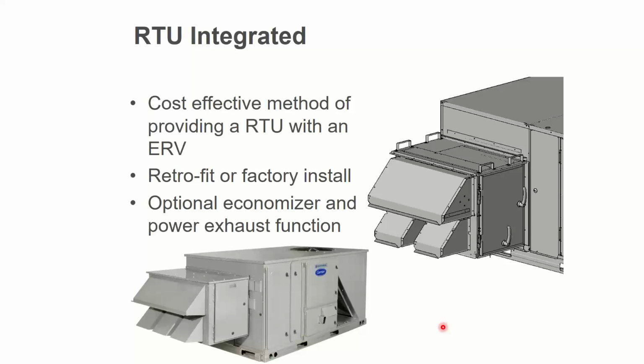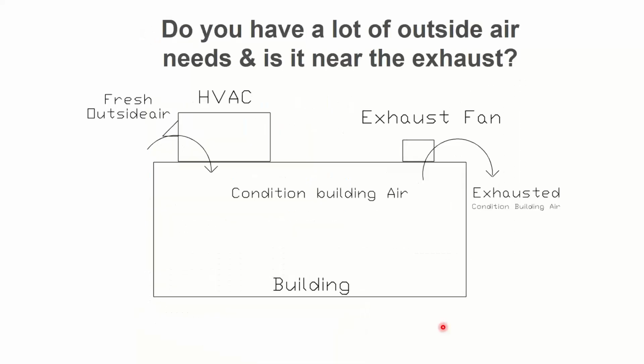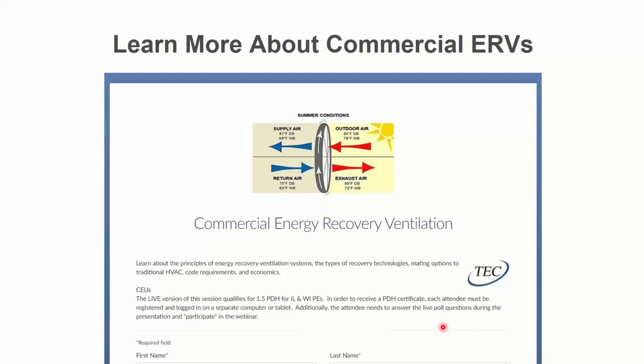And then there are small ERVs that you can bolt onto the side of an existing rooftop. We don't do that very often for the simple fact that most rooftops are already oversized. And when I put an ERV on, I need less cooling, so that makes that problem worse. Sometimes we do it when there's a change of usage of the space. Hey, this used to be an office building. Now it's going to be a fitness center. We need more tonnage and we need more fresh air. What can we do? Well, you can possibly keep the existing rooftop and add an ERV onto it to get the work done. So we do that sometimes. The big key, though, like I mentioned, is having the outside air and the exhaust air near each other.